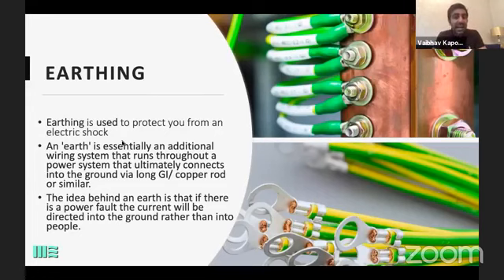The neutral, again, the black wire, needs to be earthed properly. Why? If there are any unwanted currents flowing in the red phase, yellow phase, or blue phase, the three phases of electricity we spoke about, they flow into the ground. So you need grounding for that. If you don't have grounding and you are touching that equipment, you are the one who ultimately takes that load, because there is no proper earthing. You see in the picture there is an earthing wire with a lug. This earthing wire is transferring that extra load into the ground. When we use copper rods or galvanized iron rods, that is just a medium. The wire takes that load and puts it inside the ground so that you don't take that shock.